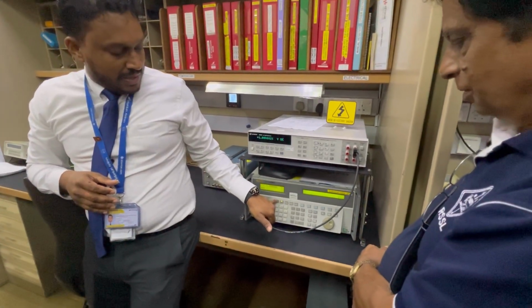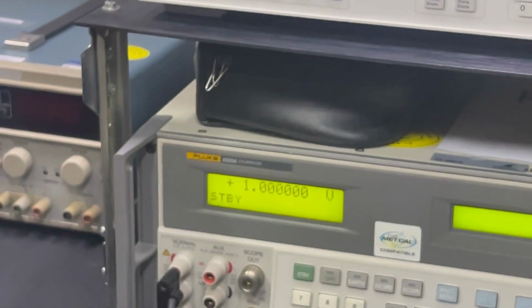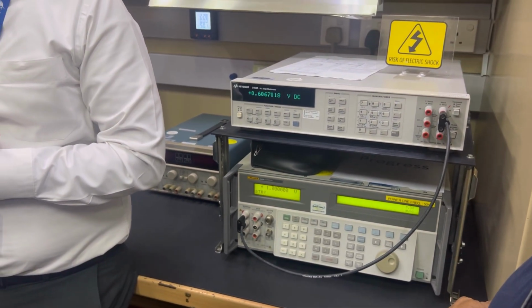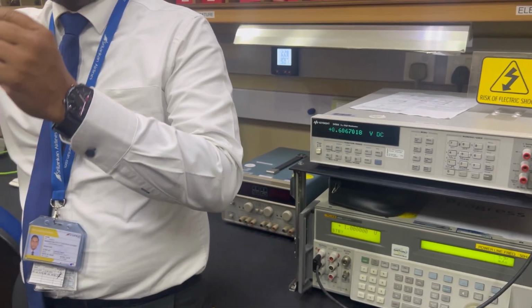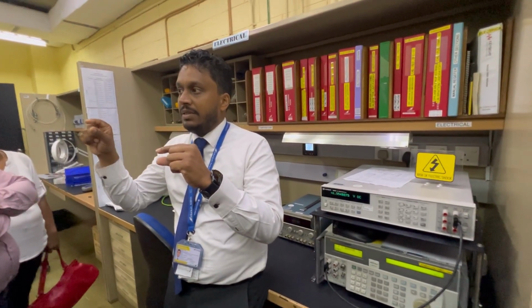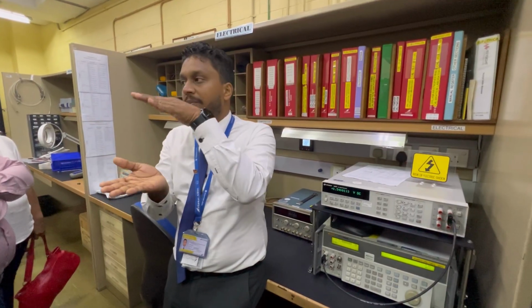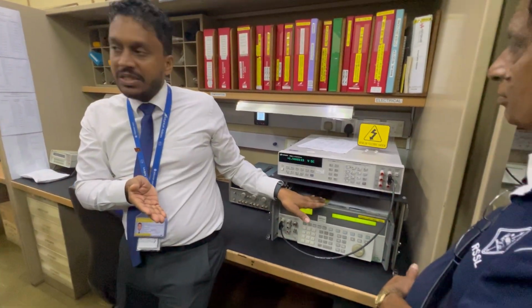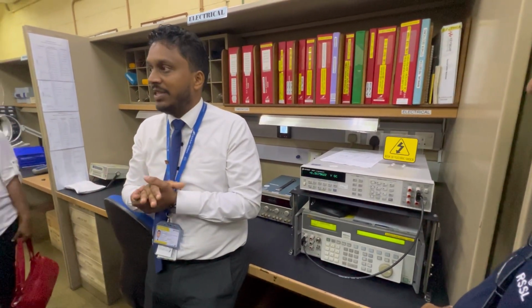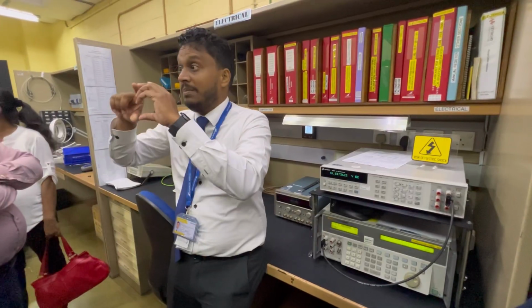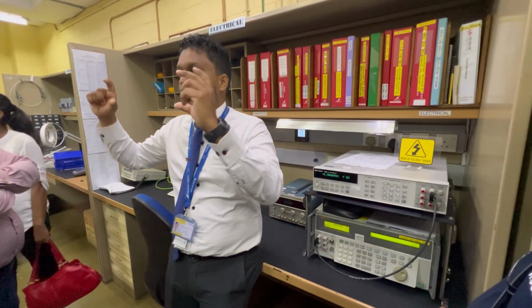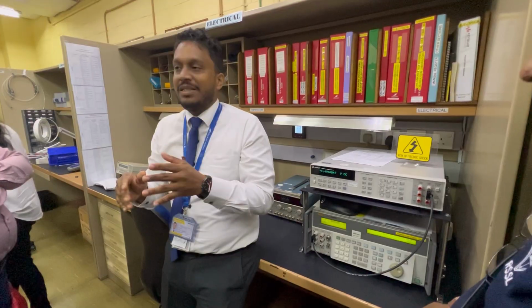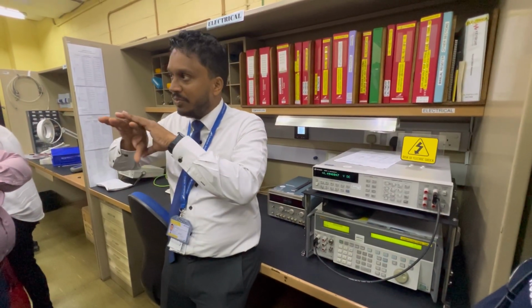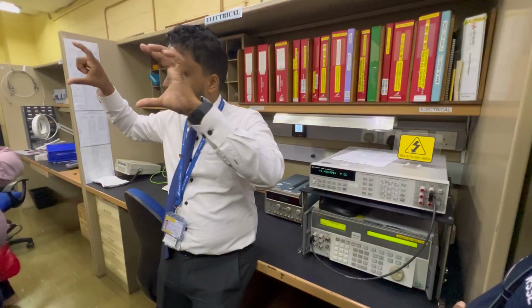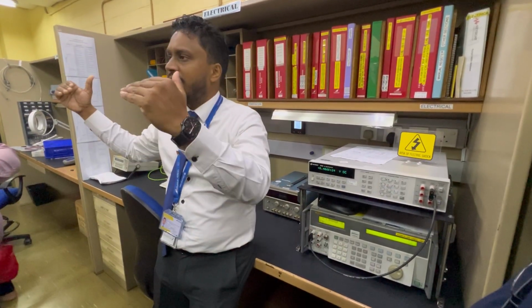So, can you take something like that? Our error level is 0.001%, something like that. What we do is draw a trend analysis, a trend curve, right? So we see the trend, and we keep 2 limits. The 2 limits will mostly be this instrument's specification limits, because the manufacturer, Fluke, will give you a thick margin, because they don't want to go into lawsuits. So they say within a year this instrument can deviate by this much. So we plot that as the limit. We can reduce it also as our requirement.